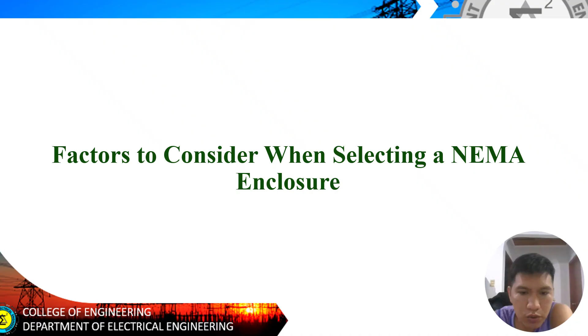Factors to consider when selecting a NEMA enclosure: first, understand the environment in which the equipment will be used. Will it be exposed to water, dust, chemicals, or extreme temperatures? Indoor environments might require NEMA 1 or 12 enclosures, while outdoor or harsh industrial applications might need NEMA 4, 4X, or 6 enclosures. When designing, we can check the environment and conditions of the location to determine whether we need NEMA 1, NEMA 3, NEMA 12, and so on.